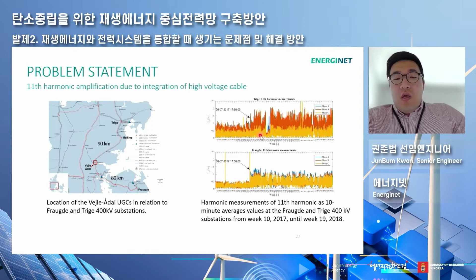And the sea cable, array cable, can create 11th harmonic frequency, and LCC HVDC. Of course, they have the filter, but LCC HVDC, in the next 5 to 10 years, will need some more tuning. And if they are not tuned precisely, or because of the operation point, if there is amplification of high frequency near the wind farm, the residents actually suffered from high frequency, and they have registered a lot of complaints.